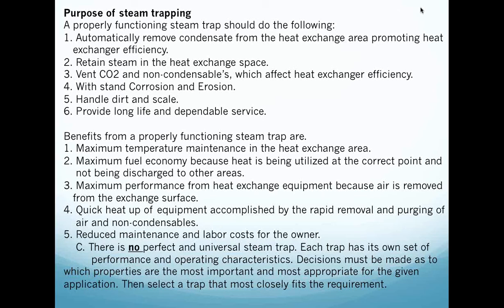And when you touch your steam trap population, I would ask that you also touch your strainers and make sure they get blown down. It's unfair, again, to blame a problem on a steam trap when you have a strainer in front of each of your traps. I went in and did an audit on a facility that was built in 1989, and the steam traps in the facility had never been put in with nipples and blowdown valves, and so those strainer screens were completely filled up with garbage, and unfortunately the traps in certain portions of that facility did not work, but the strainers never ended up being put on a maintenance schedule.